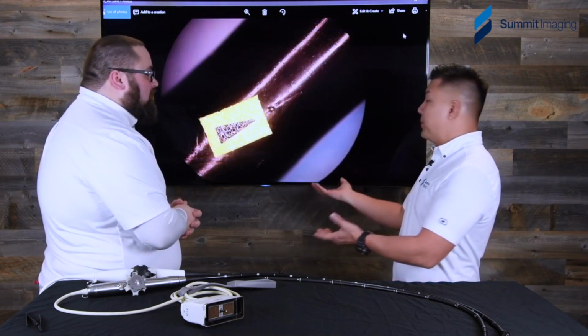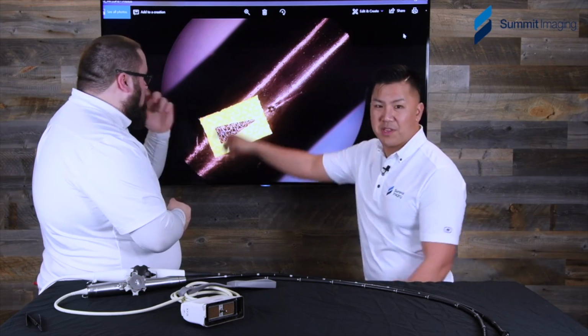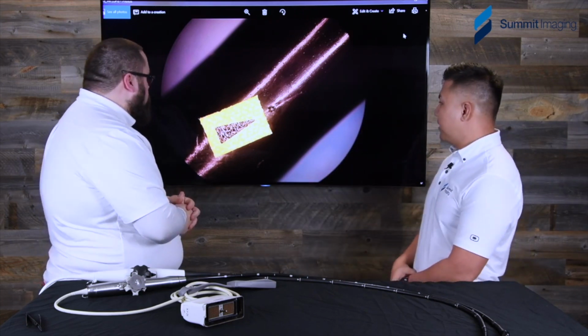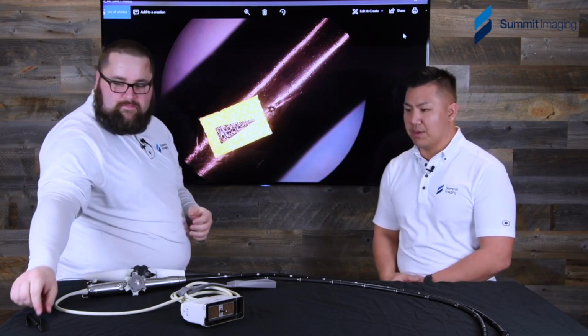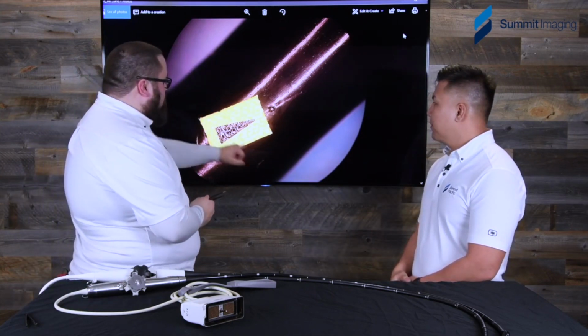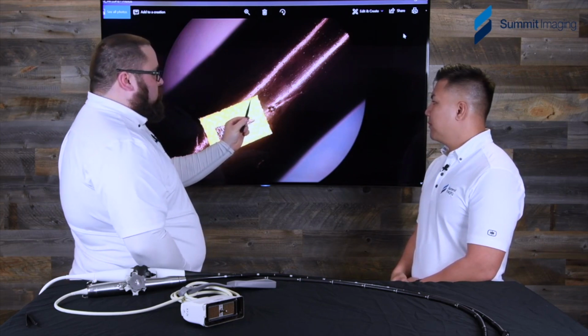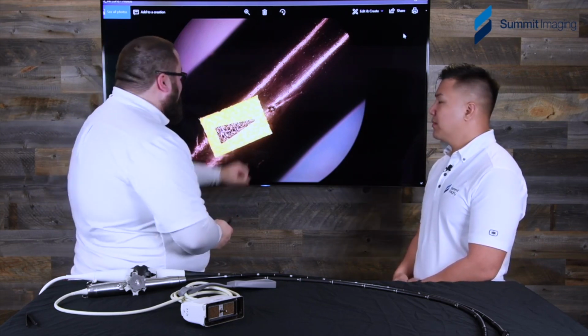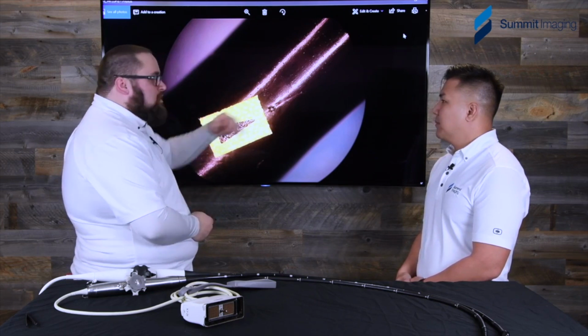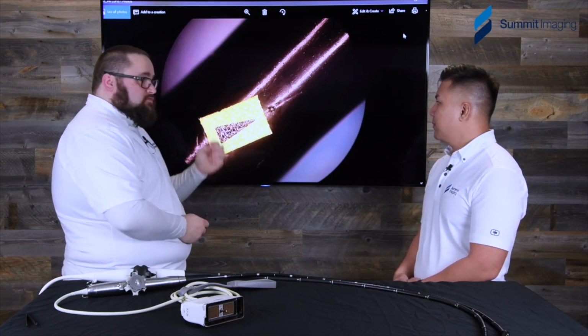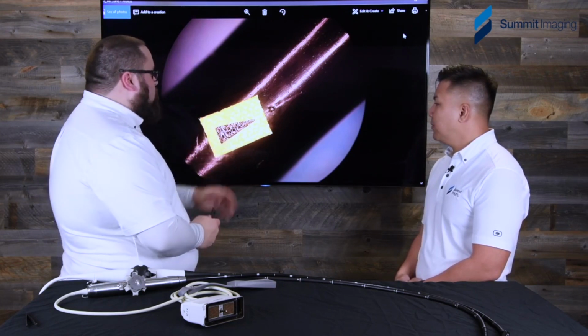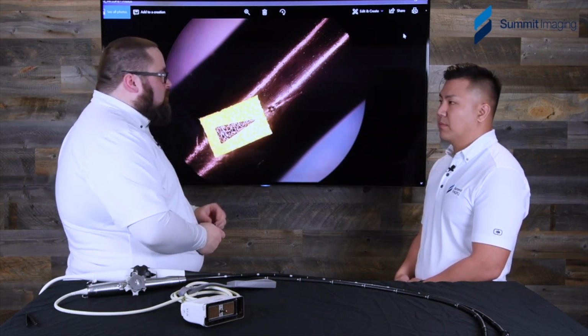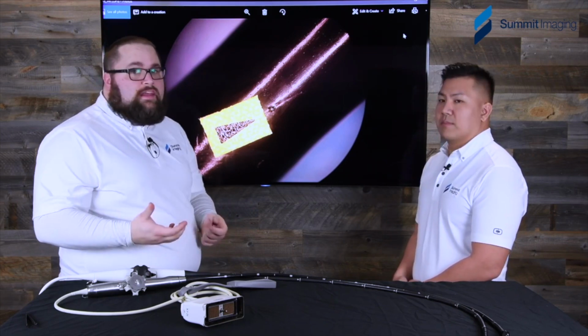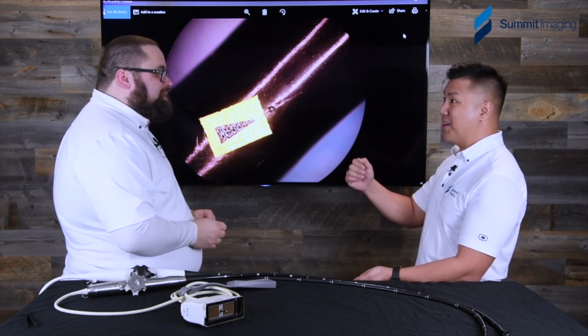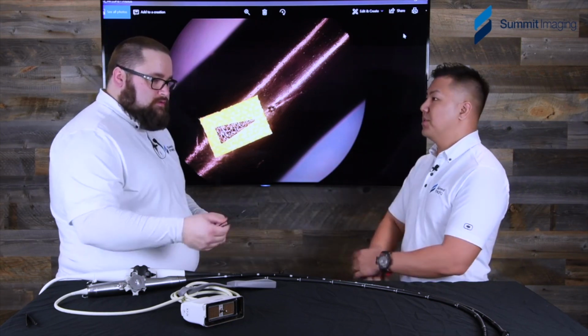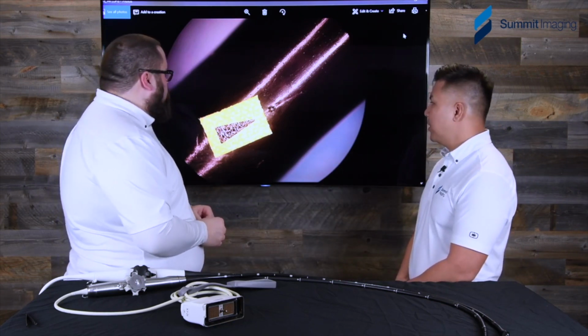So this is what we've been talking about, and it's a circle because we're underneath a microscope here. Kyle, tell us about what's going on. That tip right there, this little yellow sticker, is probably about the size of the tip of those tweezers I just happen to have on the table. And that bite mark might be about the size of a needle hole. It's going to be very hard to detect with the naked eye, but that bite mark can let in 2 or 3 drops. And 2 or 3 drops of Cidex or OPA can start doing a lot of damage to the transducer. Especially hanging upside down, it enters here, gets to the crystal, goes up to the head. You start seeing a lot of failures there.